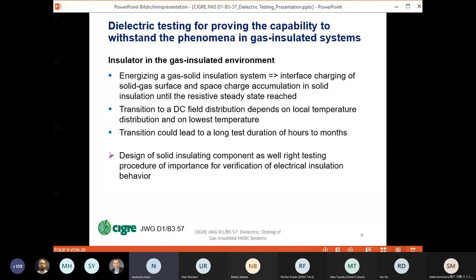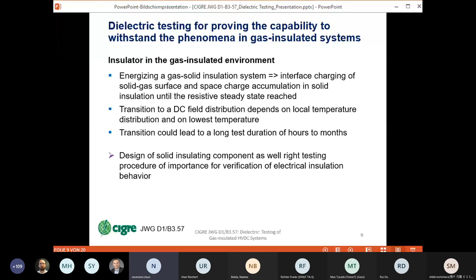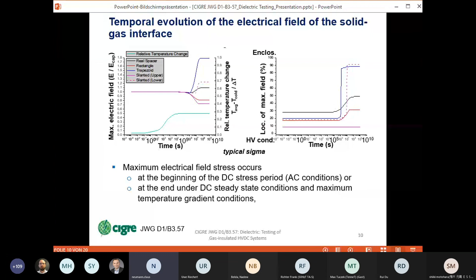That means the design of the solid insulating components, as well as the right testing procedure, is of importance for the verification of the electrical insulation behavior. Let's have a look at the temporal evolution of the electrical field at the solid gas interface. Here you can see the evolution. On the left-hand side, the maximum electric field is normalized. The light blue is the relative temperature change, and you can see here that the maximum electric field stress occurs at the beginning of the DC stress period or at the end under the DC steady state conditions and the maximum temperature gradient conditions.